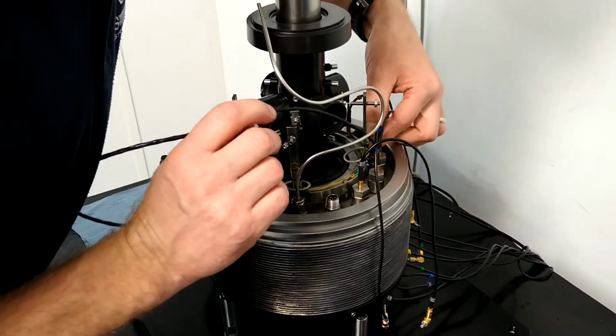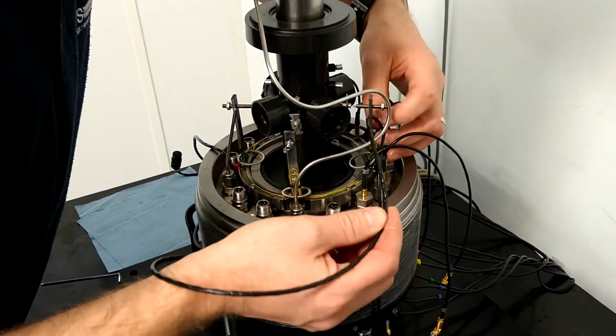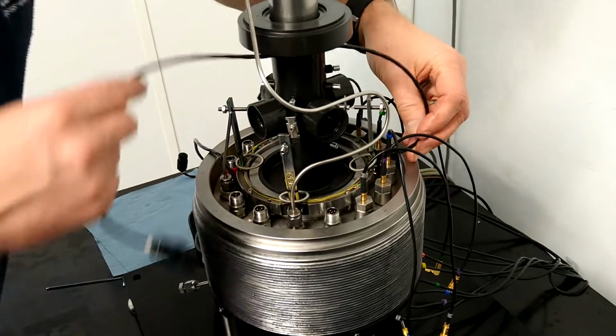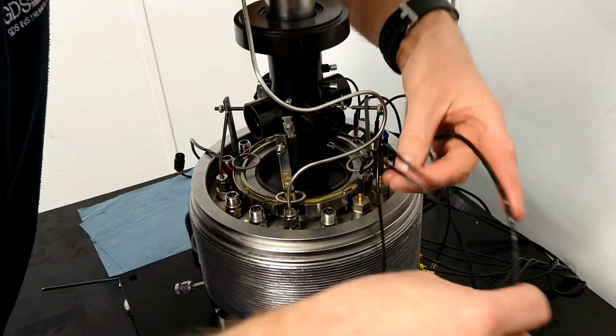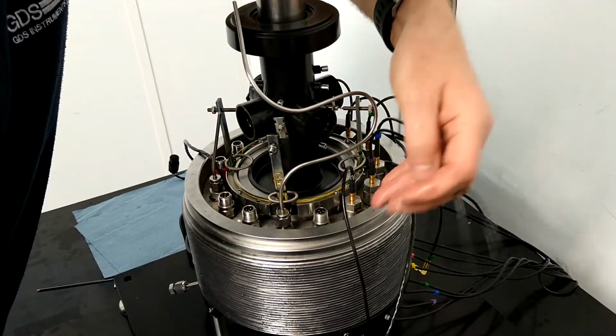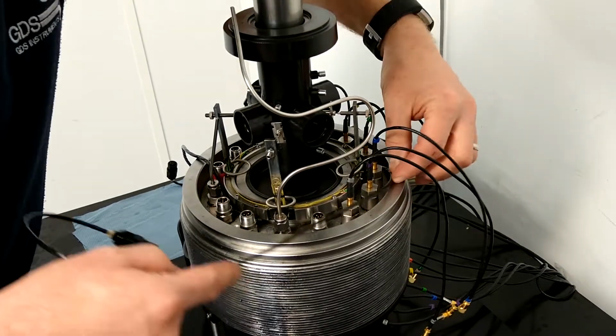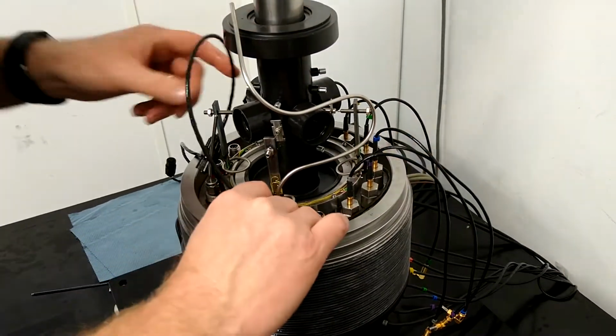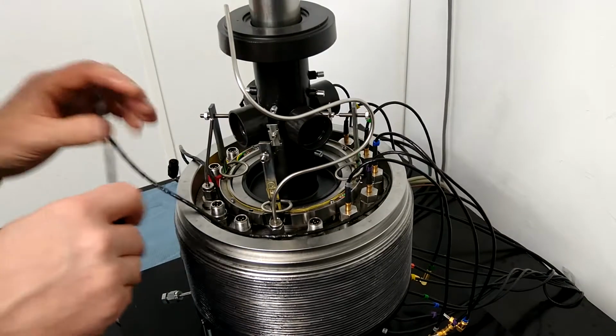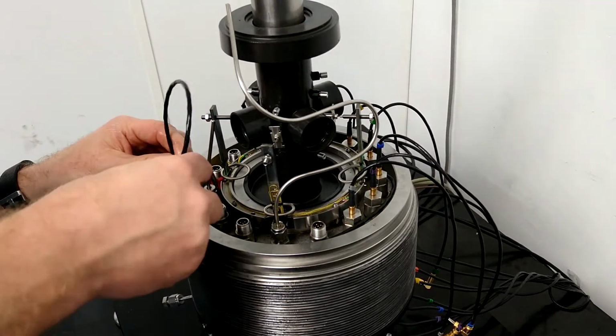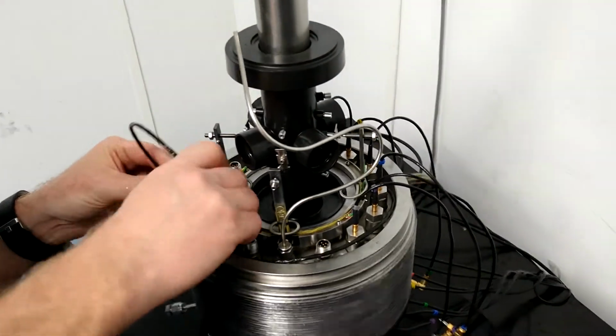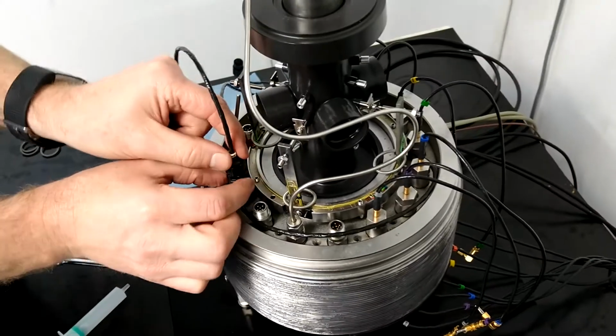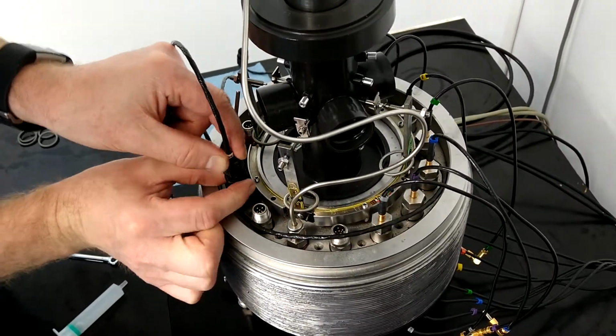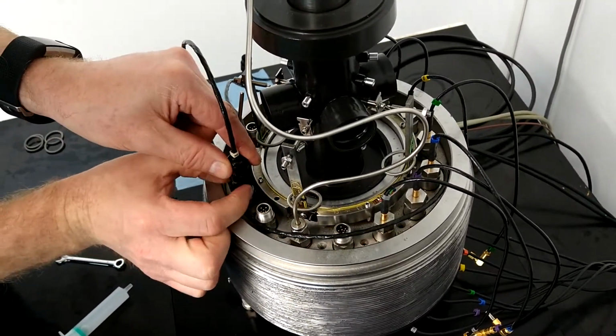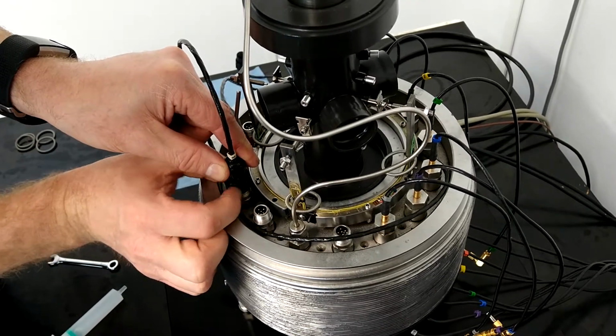Connect both the X and Y plugs into the corresponding feed-through, identified from the cable identity tag located on the exit cables from the underside of the cell base. To connect the feed-through plug, lightly insert the plug into the correct orientation. The plug should locate in place by dropping down slightly. Do not force the plug further, as it will locate more securely when the collar is tightened.